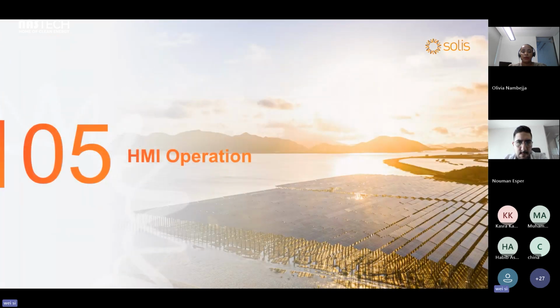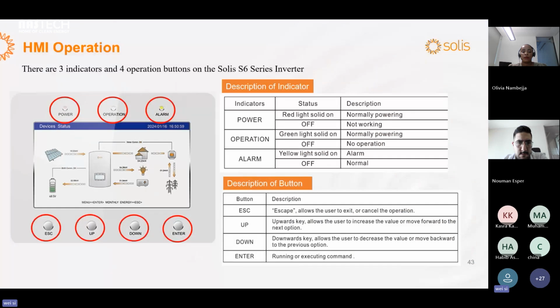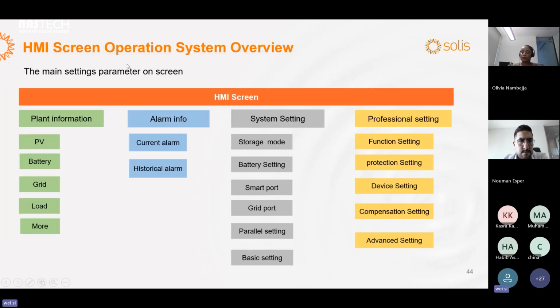Okay, it is about the HMI operation. We have 3 lights and 4 buttons to control the whole system. So it's the system overview, plant information, alarm info, system setting, and the professional setting. You can set the storage mode, battery setting, smart port, grid port, parallel setting, and basic setting under the system setting.